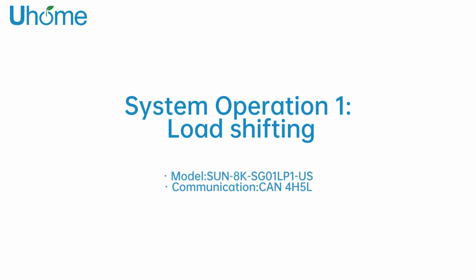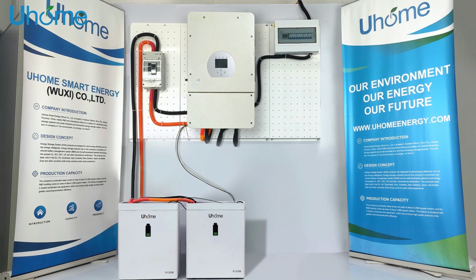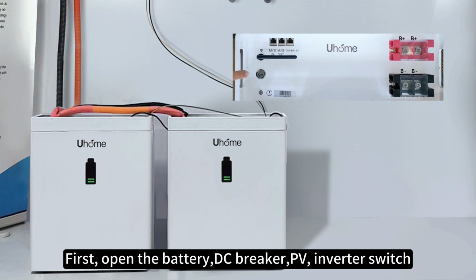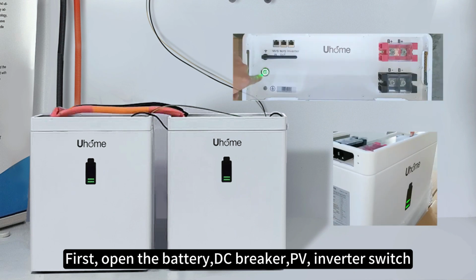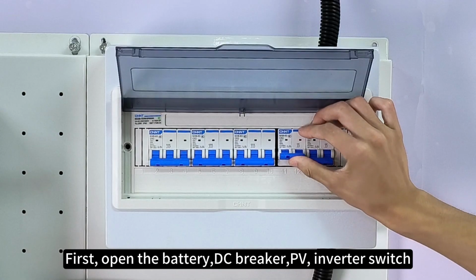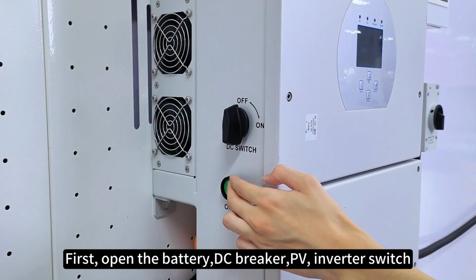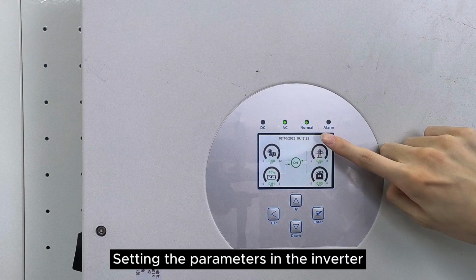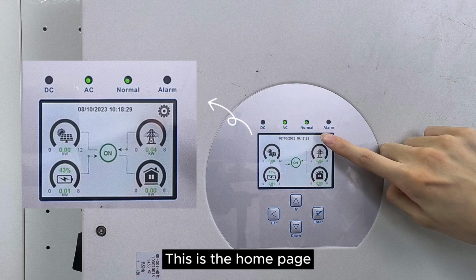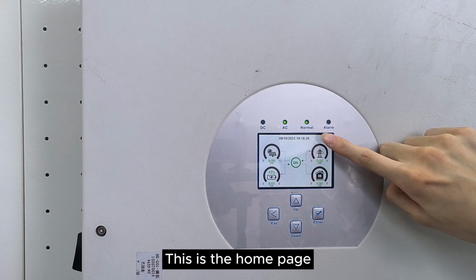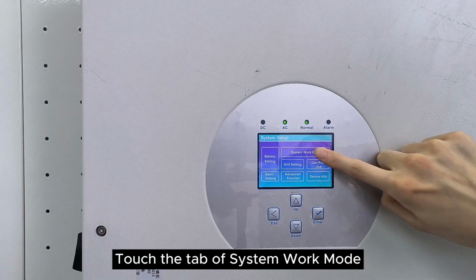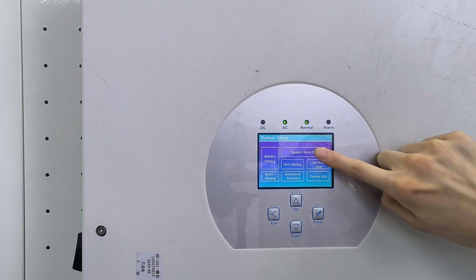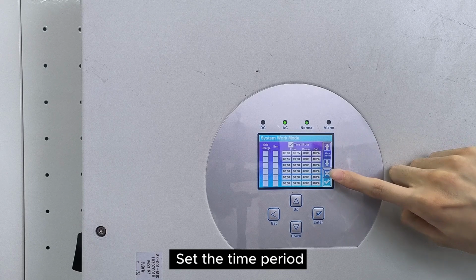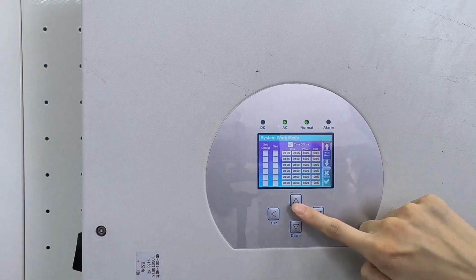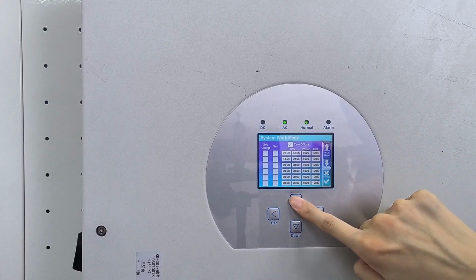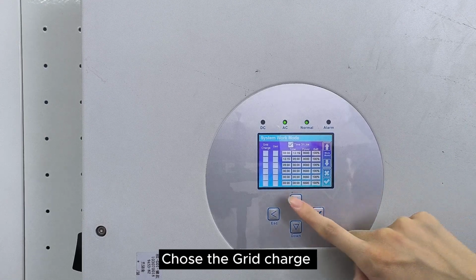System Operation 1, Load Shifting. First, open the battery, DC breaker, grid, PV, inverter switch. Setting the parameters in the inverter. This is the home page. Select Settings. Touch the tab of System Work Mode. Set the time period. Choose the grid charge.